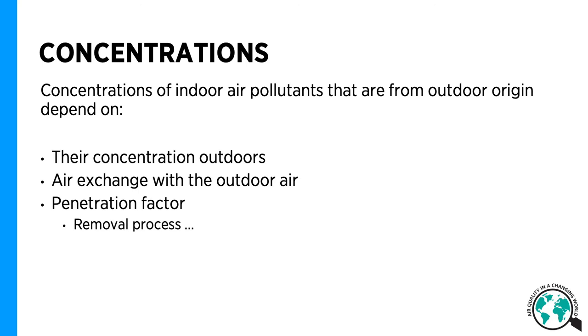For indoor aerosols coming from outdoors, the outdoor concentration is the main key factor. If it is higher outdoors, then we expect to have higher indoor concentration. The air exchange between indoor and outdoor air is another factor, and if this process is faster, there is a quicker response between the indoor and outdoor concentration. This response is shorter when we have a higher exchange rate, and this will be demonstrated later in these slides. The penetration factor is another important factor — if we have higher penetration or more leakage in the building structure, then we expect higher concentration in the indoor environment. The removal process again removes indoor aerosols from the indoor air via deposition or ventilation rate.